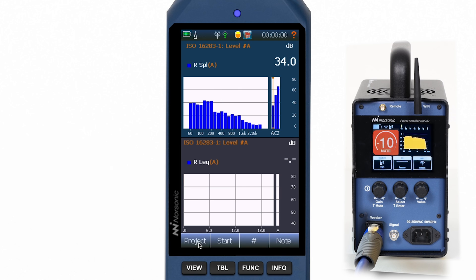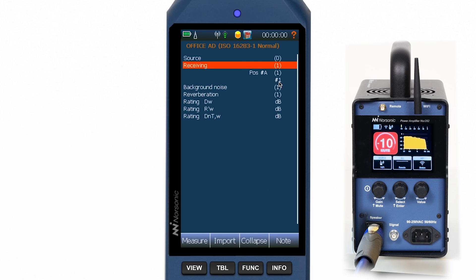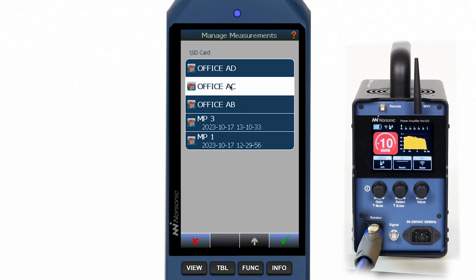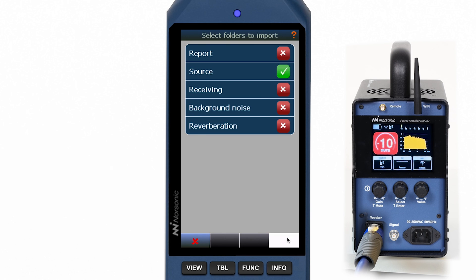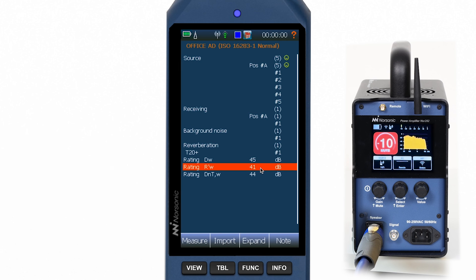Let's now have a look at the project overview. Here we see all data acquired so far. Previously we had measured the sound insulation from the same source room into another receiving room using the same gain setting on the amplifier. We can now import the sending room data from the previous project. All calculations are done on the fly, which means as new data comes in or as input values like volume are changed.